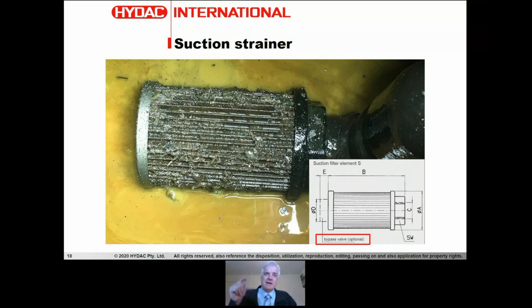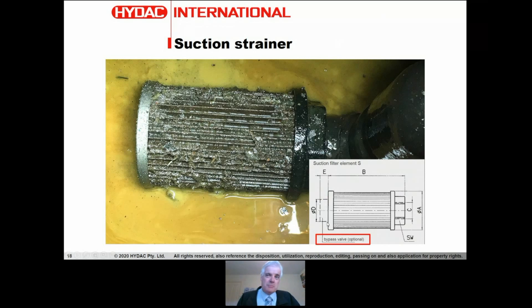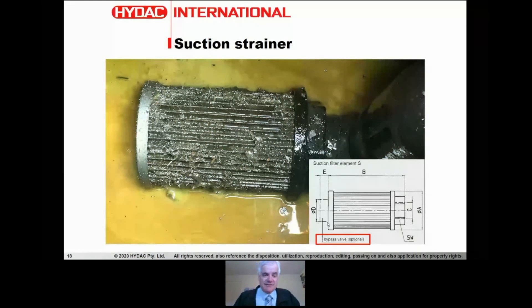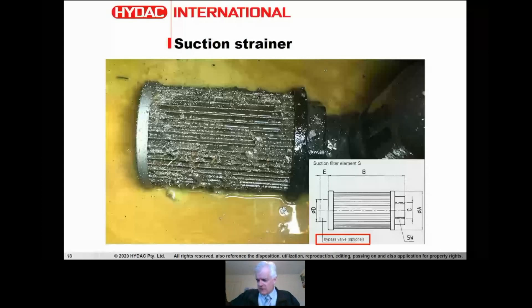A suction strainer won't clean your oil - apply filtration elsewhere. One interesting product we have is a suction strainer with an optional bypass. The model code gives you an optional bypass: if the strainer clogs, a spring-loaded valve opens, allowing the pump to draw fluid. It won't be clean fluid, but it'll keep the pump running a little longer. A bypass is available as an option in suction strainers.